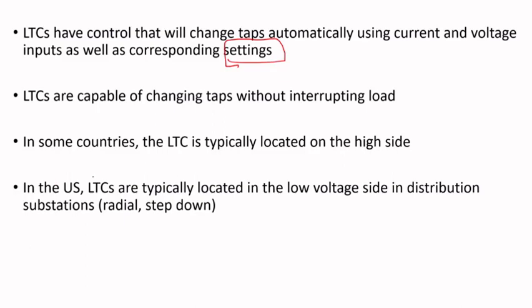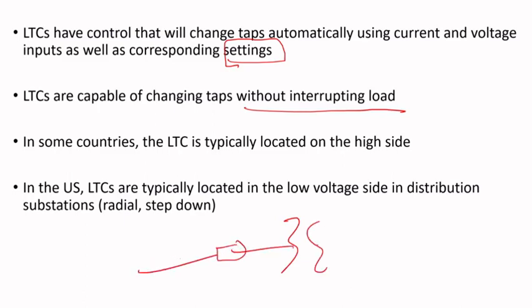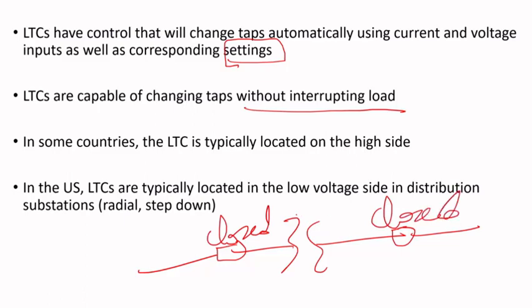Unlike the de-energized tap changer, LTCs are capable of changing taps without interrupting load. The tap changer has sensors and controls that will change the taps based on programmed settings without dropping load. In other words, with the transformer breakers closed — current flowing, voltage present, transformer energized — the tap changer will still change taps as designed.